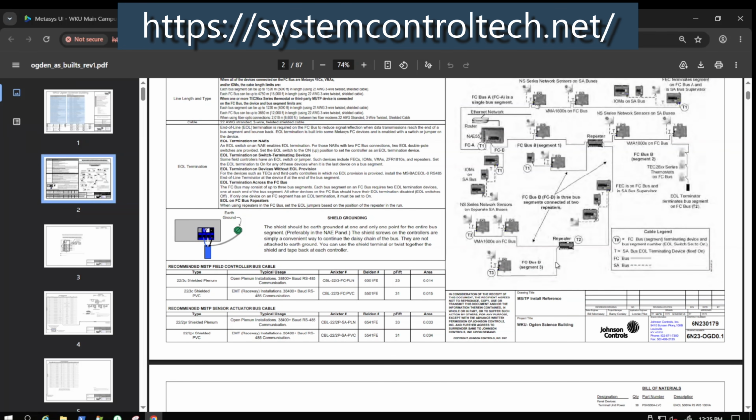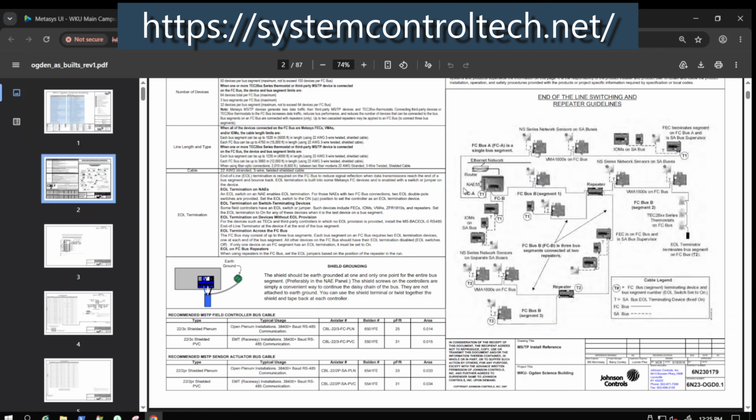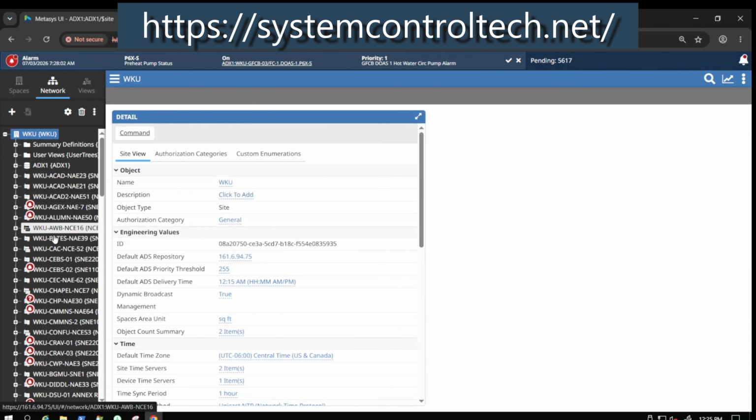And it is right here. I'm going to take just a minute to show you a little bit about how your overall system is organized. You can see here some of the network tree as far as how this is laid out. It is basically just a communication cable that goes between all of the various devices all the way back to the network engine for the building. As I had mentioned earlier, each of these devices is a network engine. Within a Tridium system, it would be a Tridium Jace, and you can have multiple Jaces, just like what you see here.